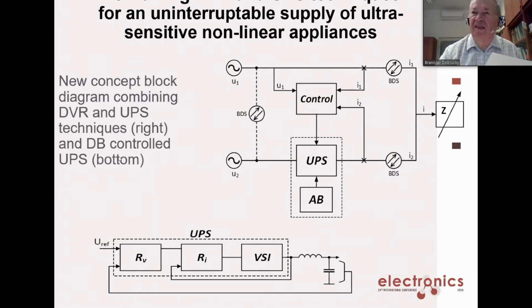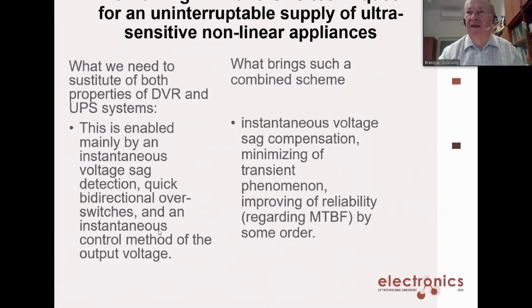As I said, the UPS will use the deadbeat controller, shown in the bottom figure. So when we need to combine both properties of DVR and UPS systems, this is enabled mainly by instantaneous voltage sag detection, quick bidirectional power switches, and an instantaneous, very fast control method of the output voltage, as I said.